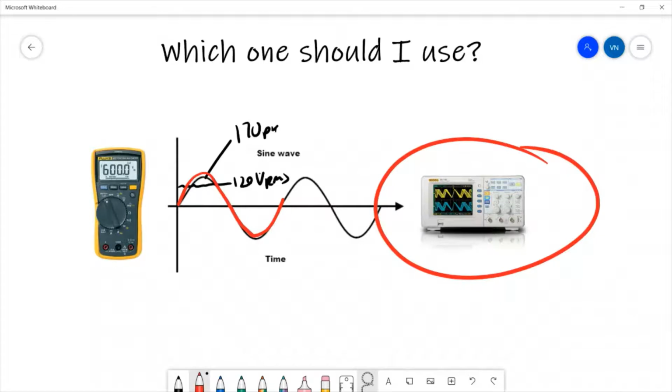And when you're using a scope, typically you may say 170 volts peak, and then you can actually measure that on the scope. However, if you're using a meter, and a meter resolves everything down to one voltage, the meters we would typically use an RMS voltage terminology, because basically off the meter we'd read 120, so it's 120 volts RMS. The meter gives you no shape information, so you don't know what the peak is or the peak to peak.